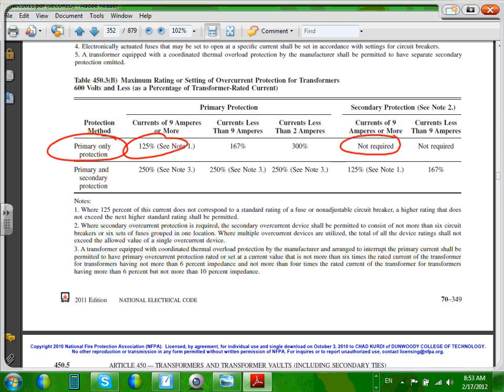Well, if you have, this is also a couple of applications that we use, primary and secondary protection. 250, we're going to use this example, and 125, these two. I want you guys to look at this one because we have an example right now using this 250 and 125 for a transformer where both the secondary and the primary are less than 600 volt. You don't have to memorize that.